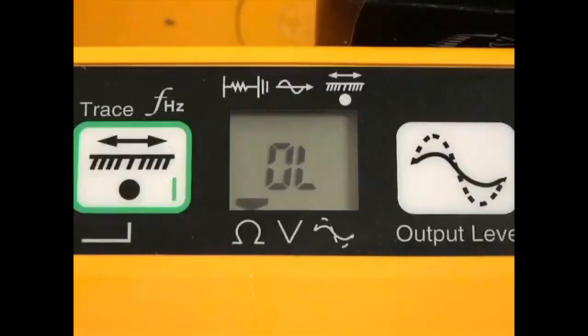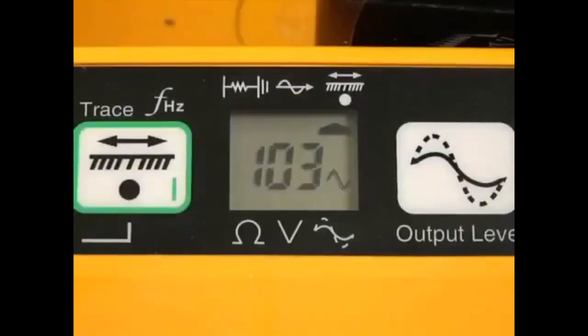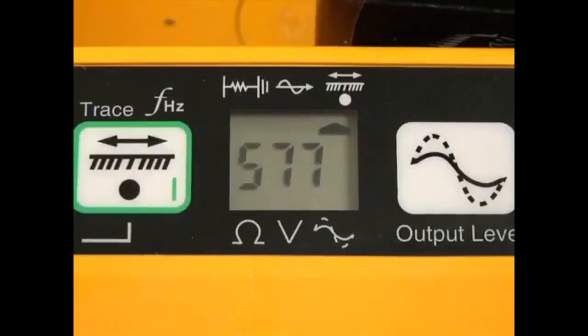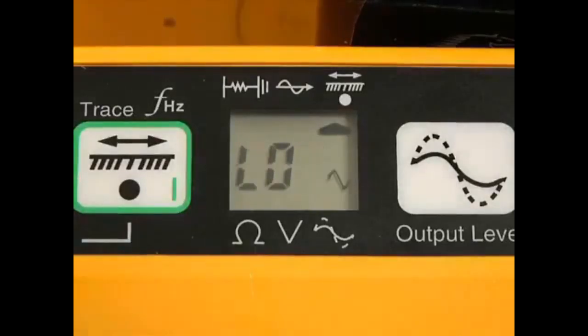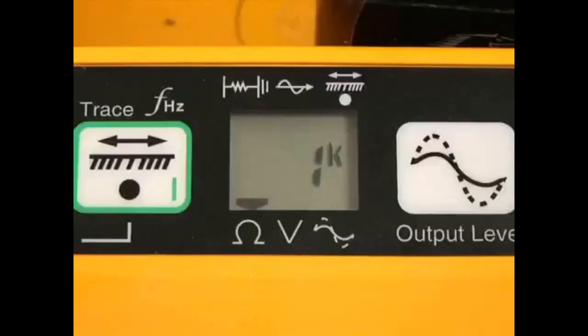You should attempt to improve the condition of the signal path. When using the direct connect method, the transmitter current level will alternately flash with the selected frequency on the display. Make a mental note of the transmitter current level before you start locating the target path. To help verify the target path, compare the transmitter current level to the current measured by the receiver on a suspected target conductor. If OL is flashing alternately with the frequency, the signal path circuit is incomplete or inadequate. The far end return to earth may be missing. Verify that there is a return to earth on the far end of the target conductor and then measure the signal path resistance again.